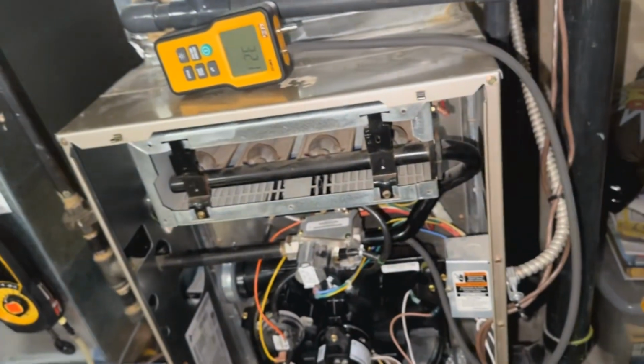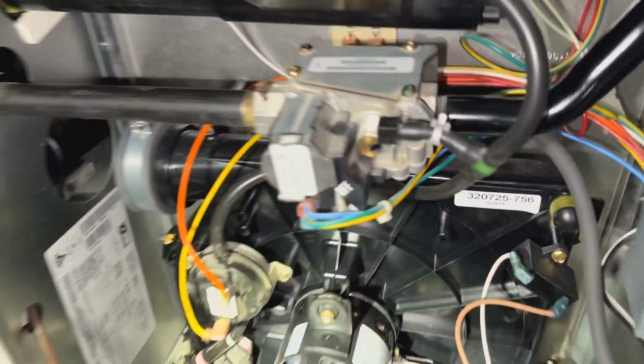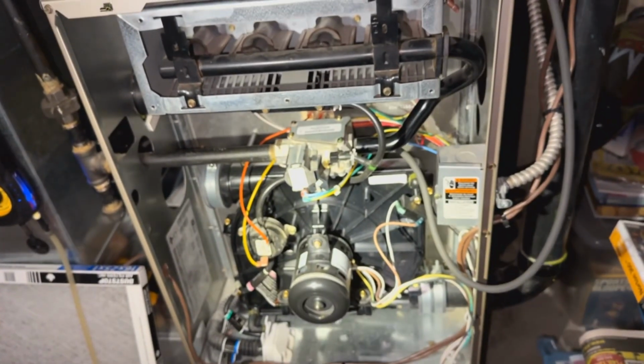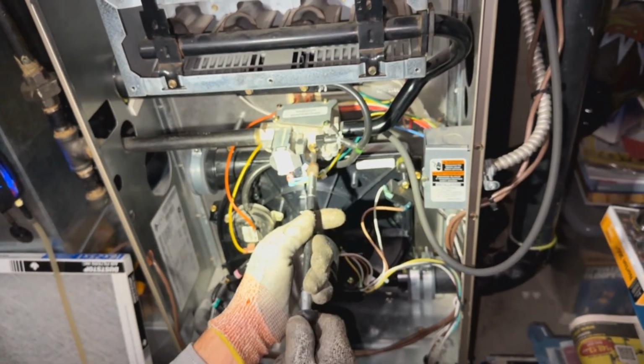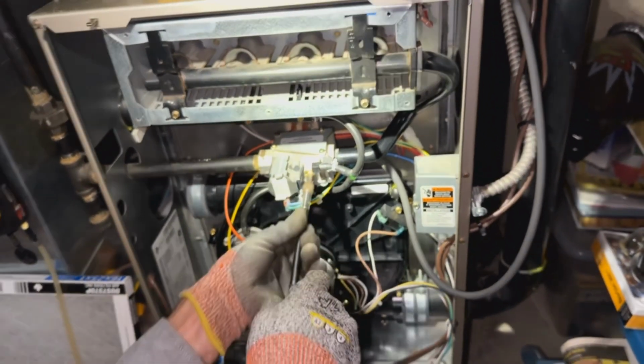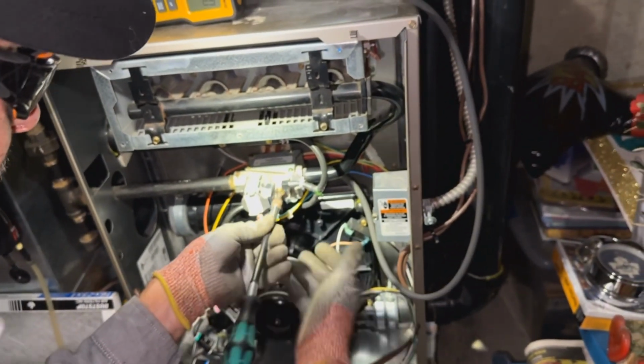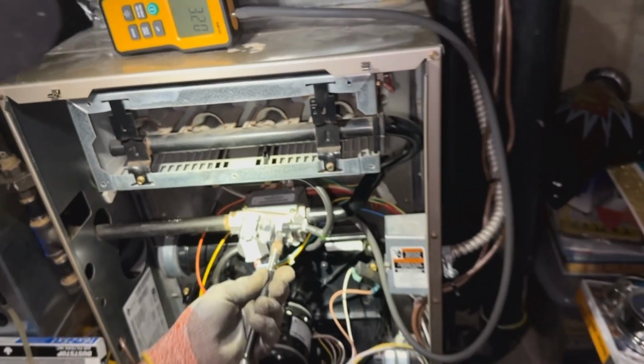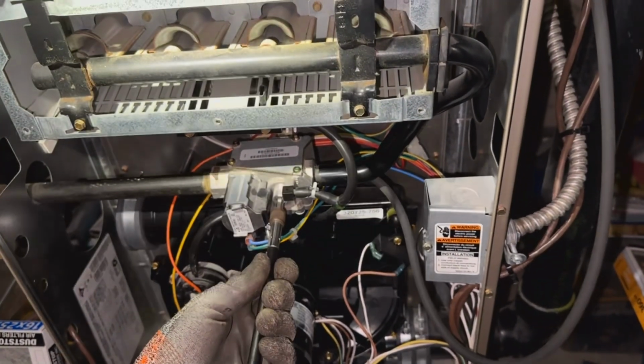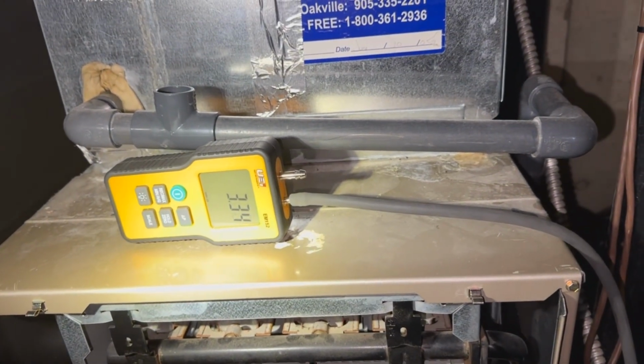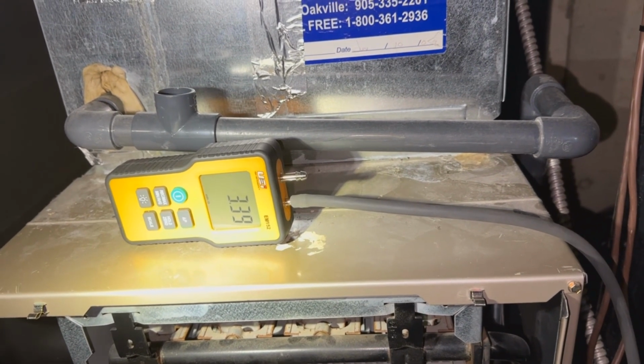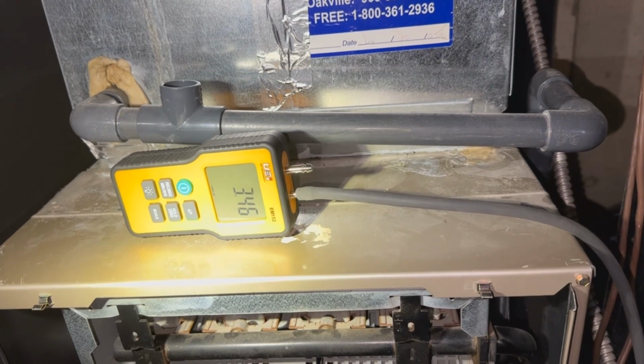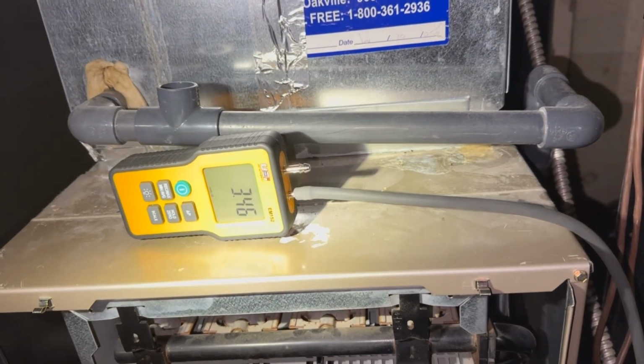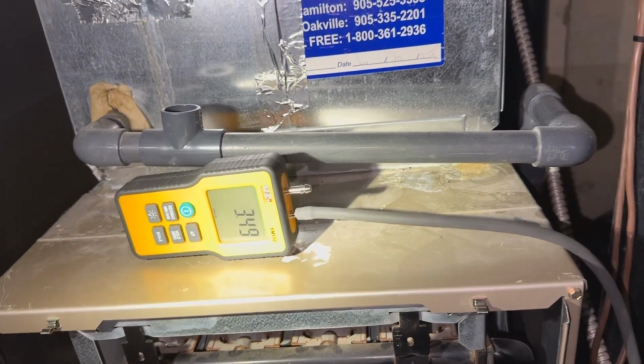So we're gonna now adjust gas pressure. That little brass cap is right off the gas valve. Have you ever adjusted this, Joe? Yeah, this morning. Alright, so you didn't crank this tight then? No. Perfect. I wish they were all like this one. So as he's adjusting this, there's a little screw on a spring in there, which adjusts the pressure. 3.2 to 3.8 is our threshold. 3.5 is a good number to set it at.